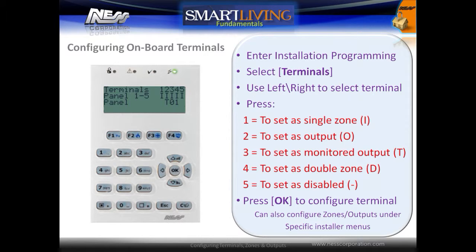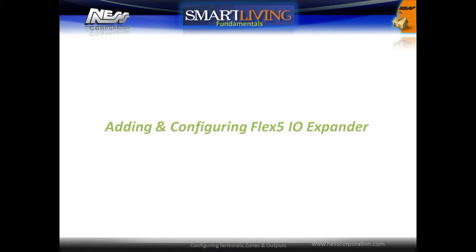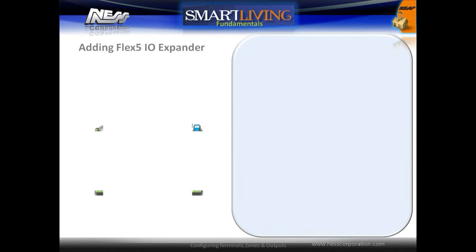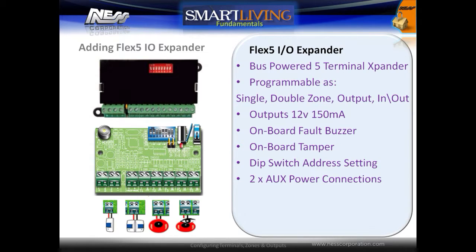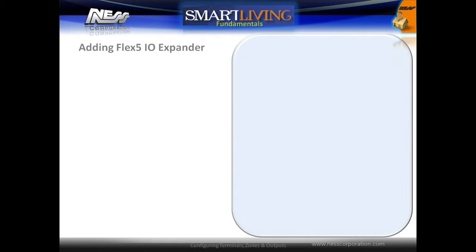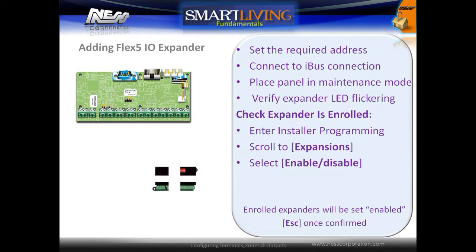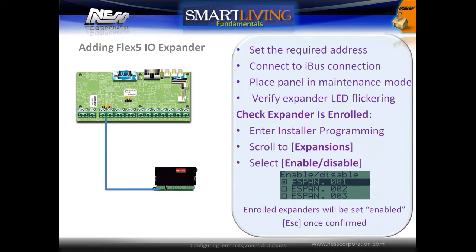The Flex 5 IO expander can be used to add additional terminals to a system. Each of the five terminals can be configured as a single or double input, output, or monitored output. To add a Flex 5 expander to the system, set the required address, connect it to the I-Bus, place the panel in maintenance mode, and then verify that the expander's LED is flashing. The system will automatically enroll any Flex 5 module attached if the system is in maintenance mode.